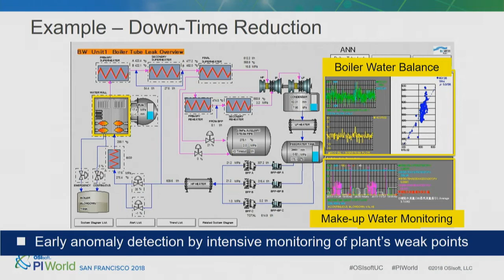As you can see, we can monitor boiler water balance in the figure on the upper right and monitor the exact amount of boiler makeup water flow in the figure on the lower right. This allows us to find any symptom of tube failures earlier than before.